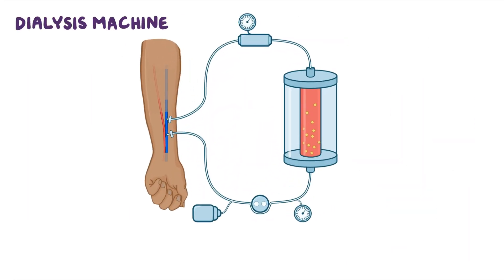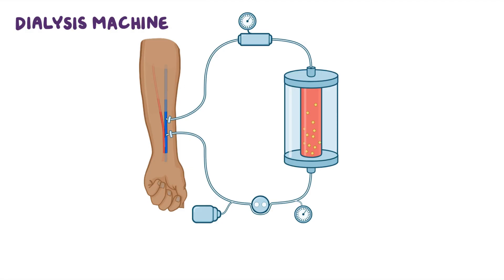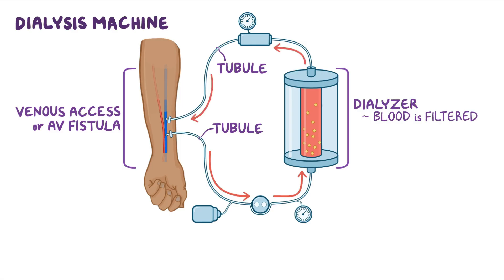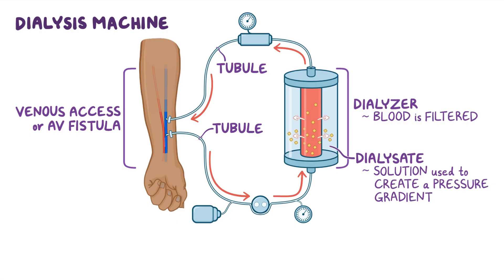To understand how this works, let's look at the dialysis machine. One of the most important components is the dialyzer, through which the client's blood is filtered. The client is connected to the dialysis machine using the venous access or AV fistula via two tubules — one takes the client's blood to the dialyzer, and the other returns the filtered blood. The dialysis machine also has the dialysate, a solution used to create a pressure gradient that makes diffusion happen.